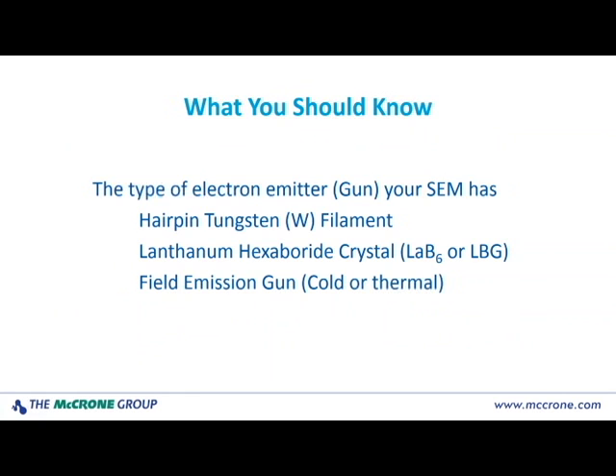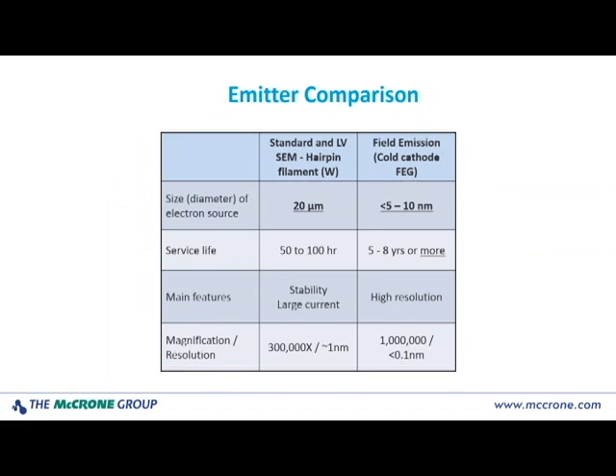You also want to find out what the electron gun or electron emitter is in your SEM. Many of them are just going to be the hairpin tungsten filament — just a tungsten wire about 120 micrometers in diameter. You also have a lanthanum hexaboride crystal, which is referred to as LaB6. You have your field emission guns, which could be the cold or the thermal variety — just a very fine sharp tip tungsten needle. So just a quick comparison of two types of emitters: the hairpin tungsten filament and the field emission guns. Your LaB6 kind of falls in the middle of these two.